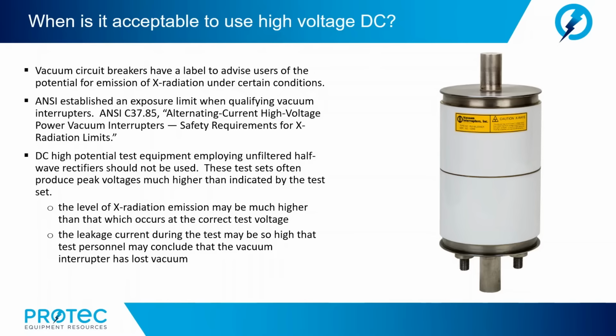So again, we do see that the design of the DC test set, full wave rectified versus unfiltered and half wave rectified, could have consequences in the testing of vacuum interrupters. And again, depending upon the vacuum interrupter, we could get false indications of a bad bottle where AC would not give us those false indications.